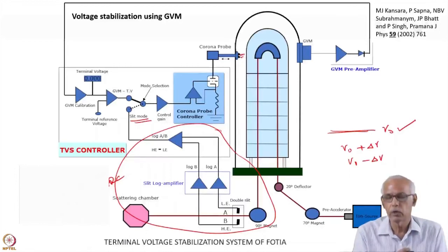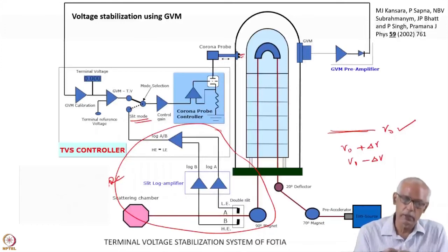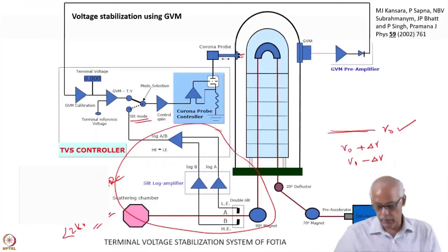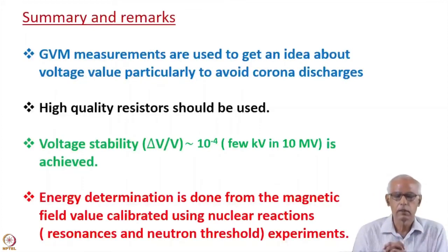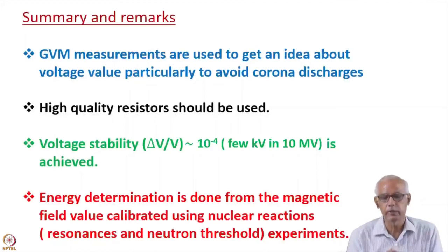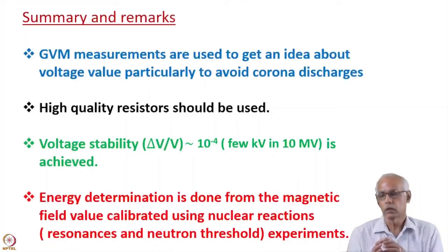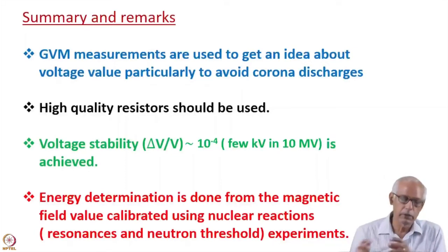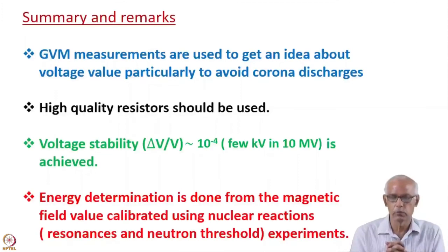This circuit was designed by MJ Kansara, Sapna Padankumar and colleagues of IADD BRC. It worked very well, and in both cases they could achieve voltage stabilization of about 2 kV at the highest voltage of 6 million volts.